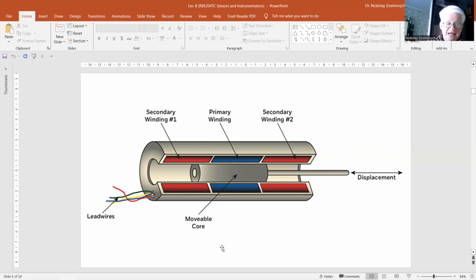Users who wish to avoid the handling of AC signals, like amplitude and phase measurement, can choose the DC LVDT, with a built-in oscillator and phase-sensitive detector. You know, both the input supply voltage and the output displacement signal are DC voltages. A stainless steel housing guarantees proper shielding against mechanical and chemical influences, as well as against electrical and magnetic interference. Special types withstand high pressure up to 200 bar or are radiation resistant. To further improve the performance, special constructions and compensation techniques have been developed.